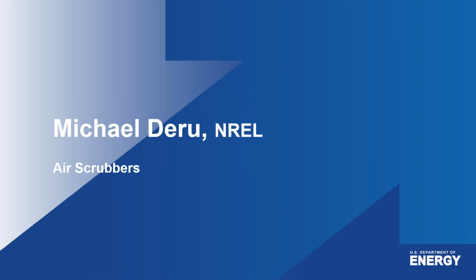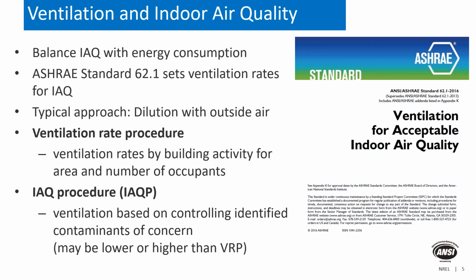All right, so let's get started here on this infrared air cleaning technology. But before, I just want to give a background on ventilation and indoor air quality, so we can have a good starting point. It's always a balance in a building to maintain good indoor air quality and energy consumption, because we oftentimes have to bring in more outside air to improve indoor air quality, and ASHRAE standard 62.1 sets the ventilation rates for indoor air quality. And so typically that's done with dilution. So we bring in more outside air and dilute the pollutants that are inside.